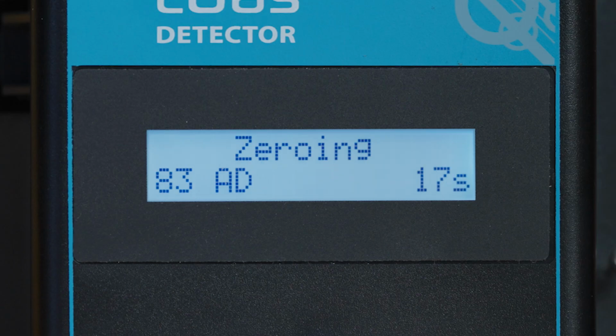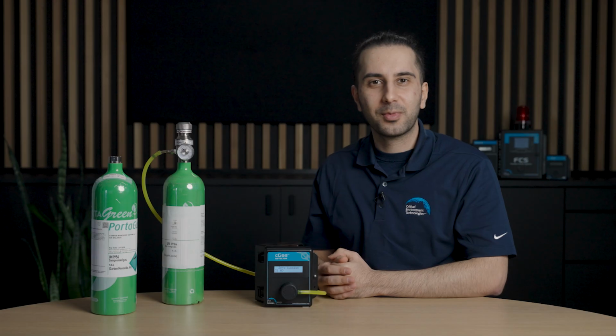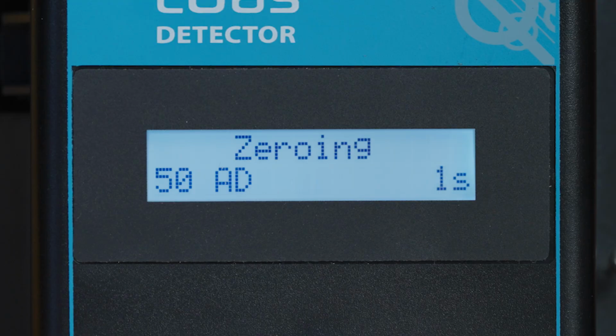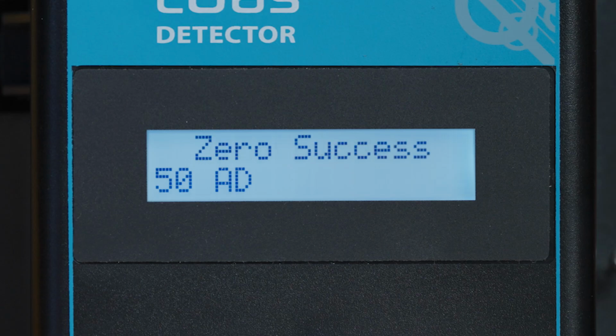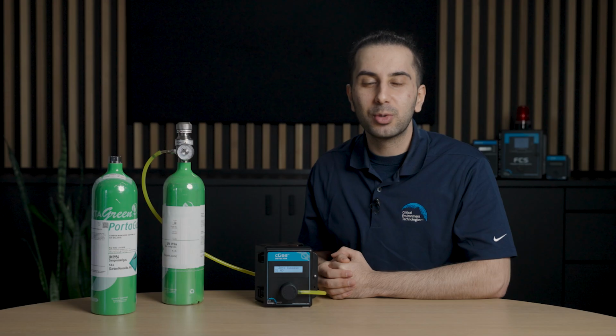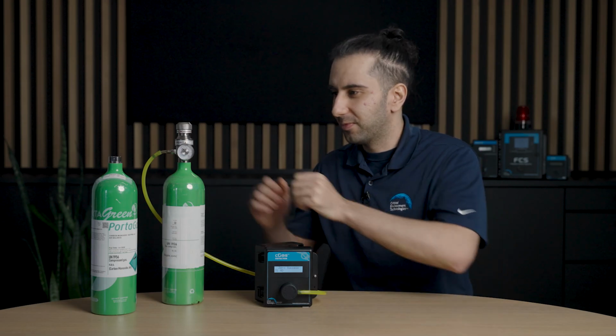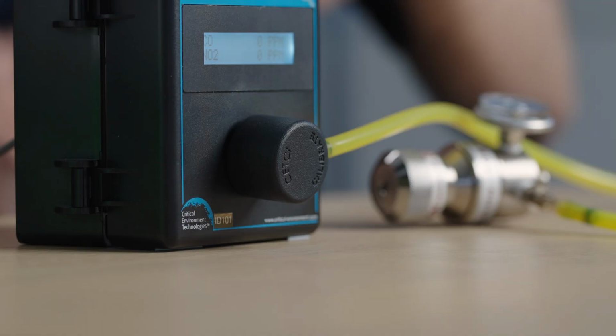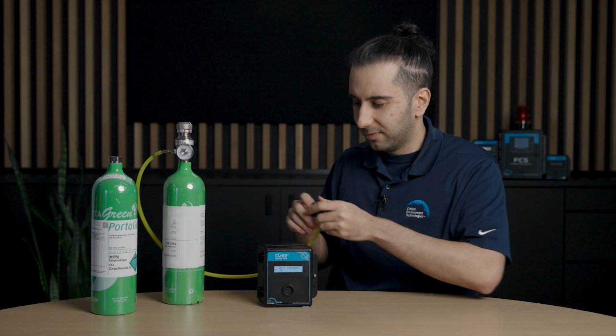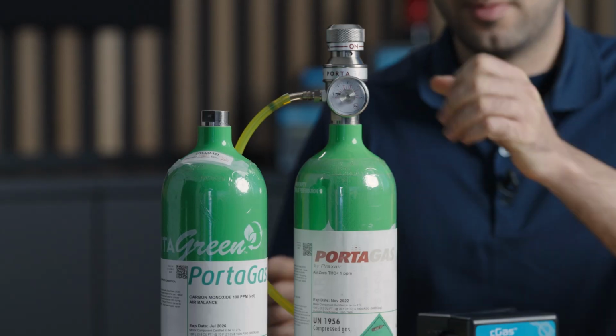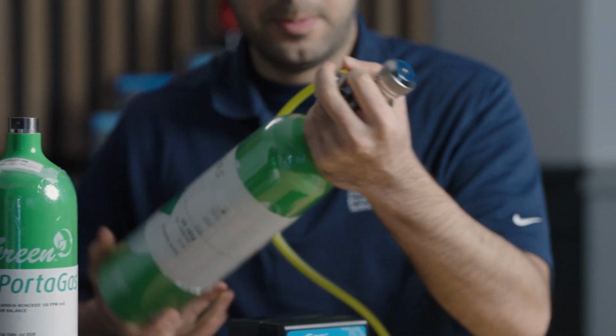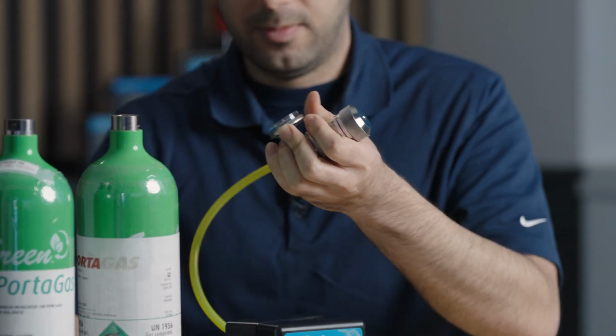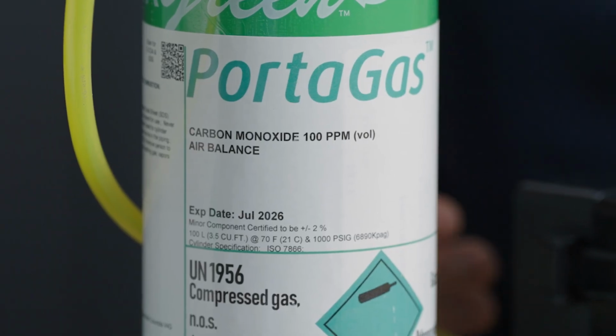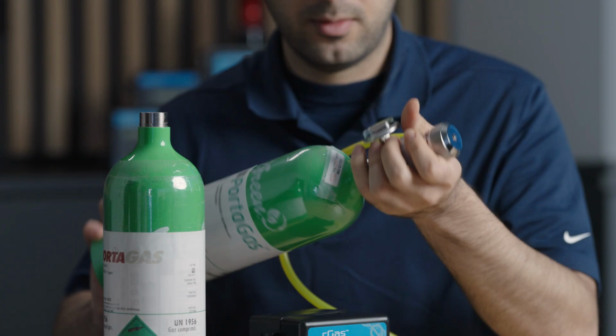A countdown will begin. Once the zeroing is complete, the display will show 0 success. You can then remove the cylinder. I will transfer the regulator from the zero gas cylinder to the span gas cylinder. I'm using the 100 ppm carbon monoxide span gas.